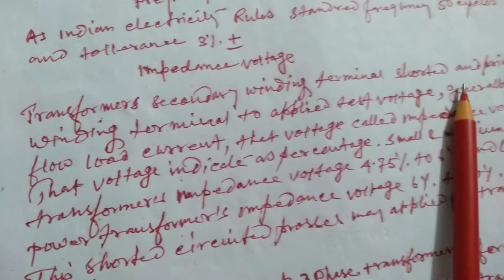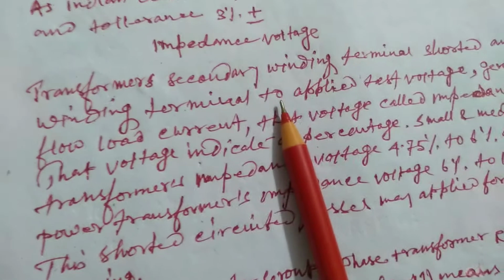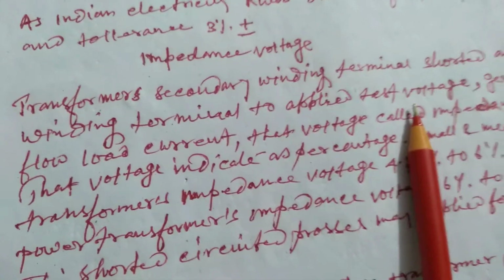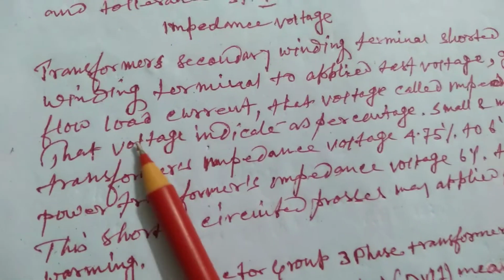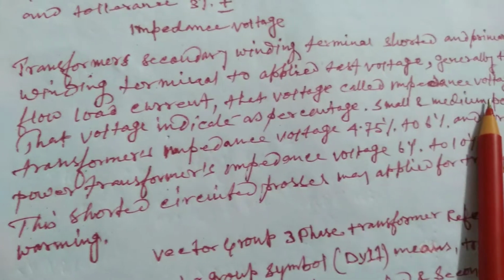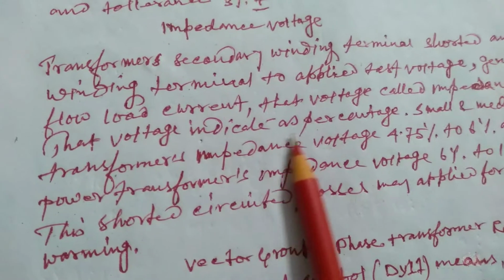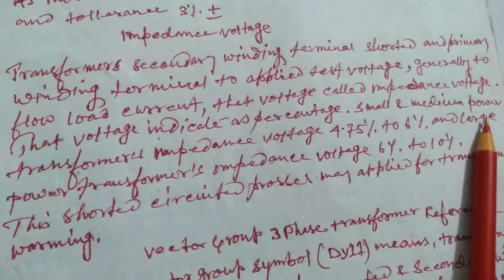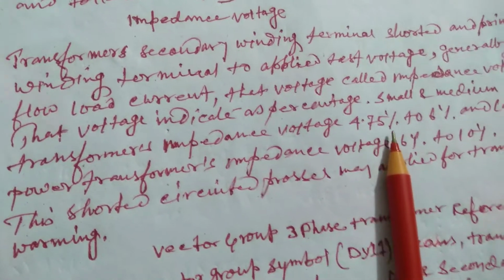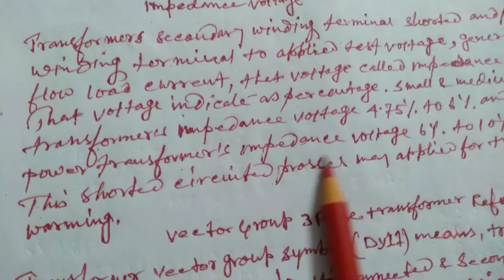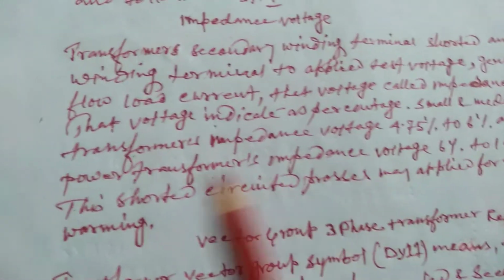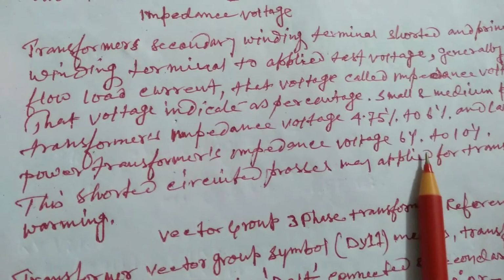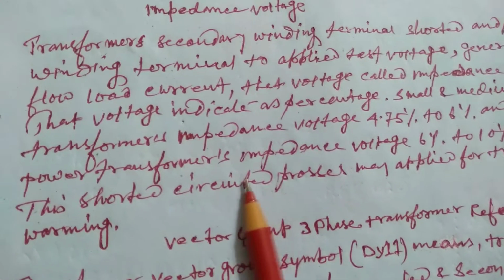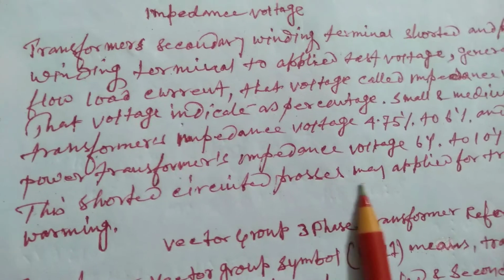Impedance voltage: the secondary winding terminals of the transformer are shorted, and a test voltage is applied to the primary winding terminals, generally enough to flow rated load current. That voltage is called the impedance voltage, and it is indicated as a percentage. Small and medium power transformers have impedance voltage 4.75% to 6%, and large power transformers have impedance voltage 6% to 10%. This short circuit process may be applied for transformer warming.